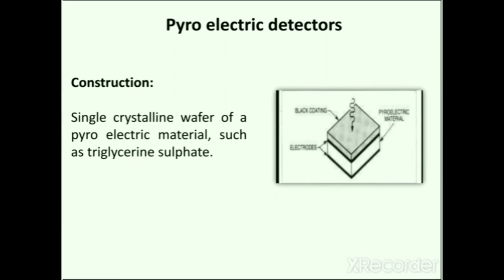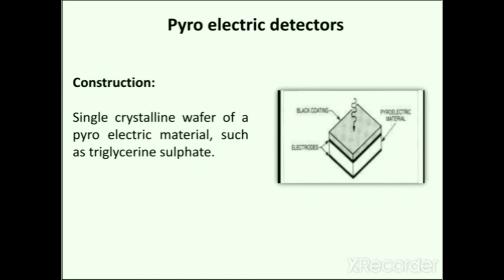Next is the pyroelectric detector, made up of a single crystalline wafer of a pyroelectric material such as triglycerine sulfate. Pyroelectric materials have the property of pyroelectricity — the ability to generate a temporary voltage when heated or cooled. Below the Curie temperature, pyroelectric materials exhibit electrical polarization. When radiation from the sample is incident upon this detector, the temperature is altered; because of this alteration, the polarization changes, which is observed as an electrical signal.